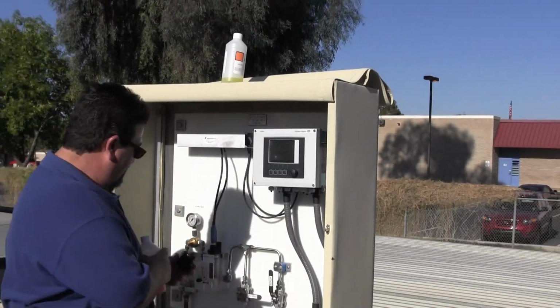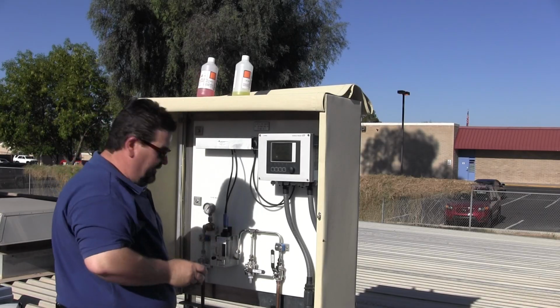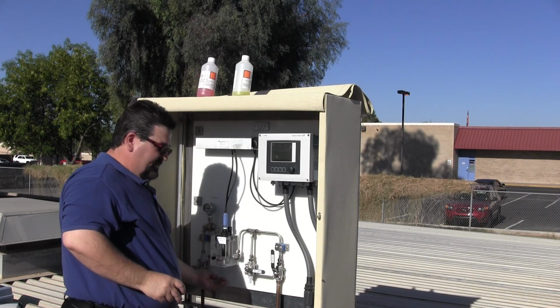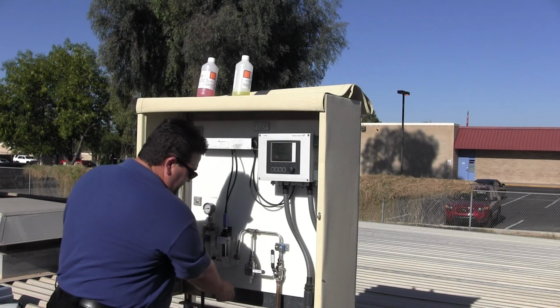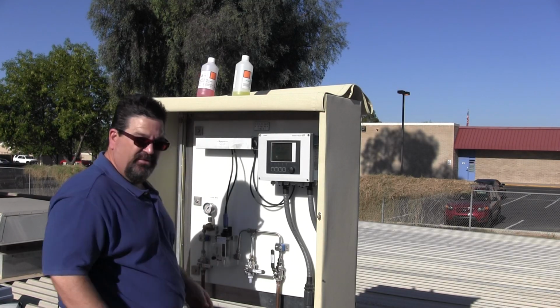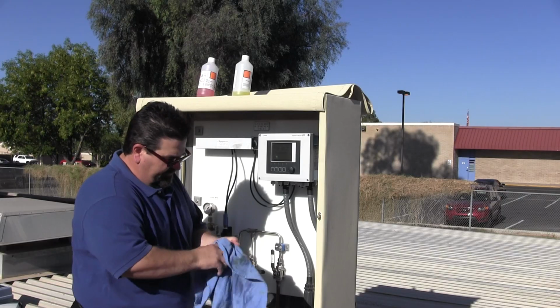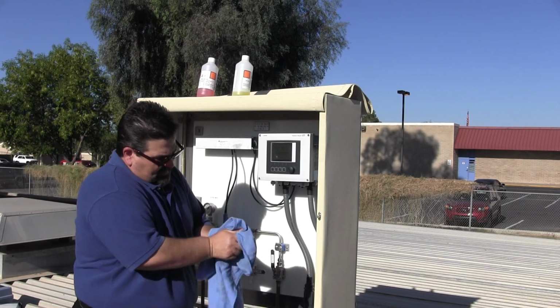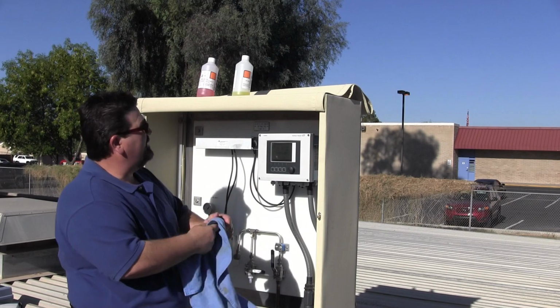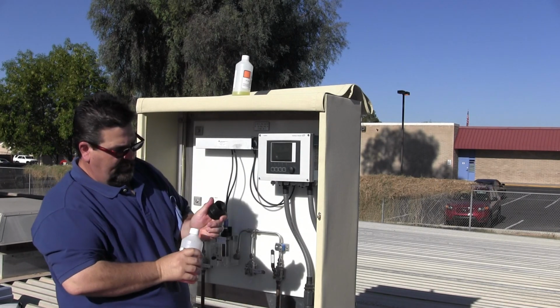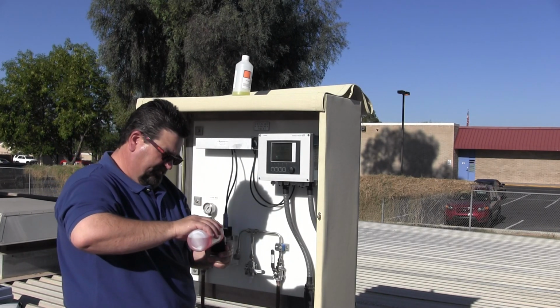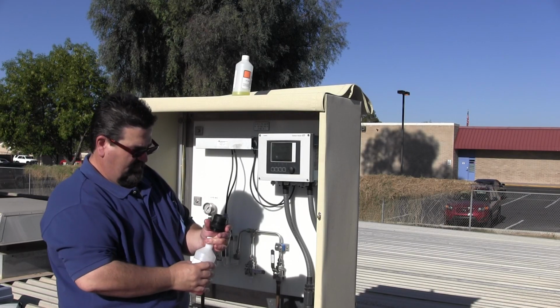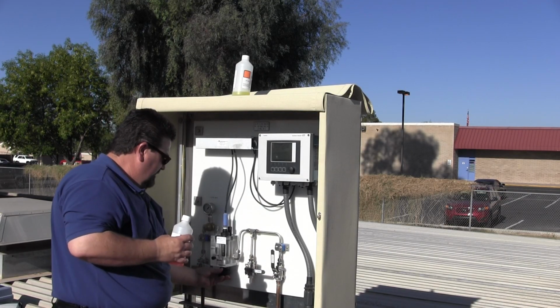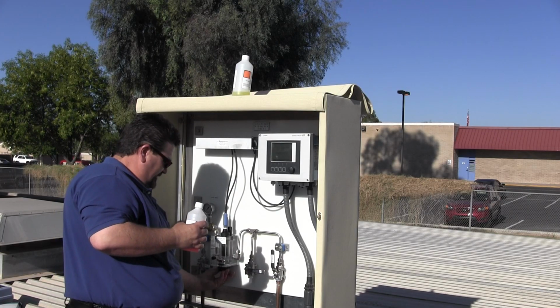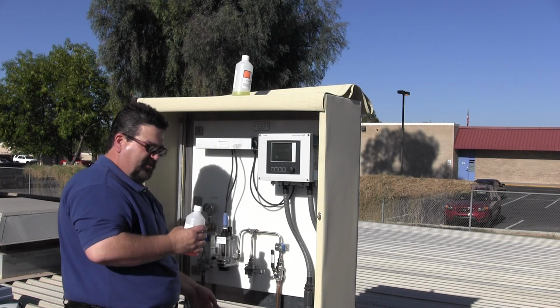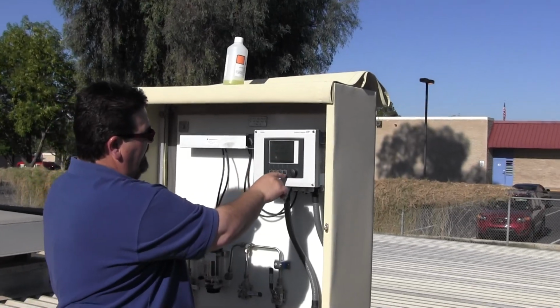discard our 7 buffer. I like to start a little water flow through the unit at this time. This helps wash the 7 buffer off the pH electrode, and I also use it to rinse off my cup. I'll stop the flow. I want to clean and dry the deep side of the cup. Fill it about 2/3 full with a 4 buffer. And reinstall it about 2 threads. Immersing the pH electrode in the buffer. I now select OK.